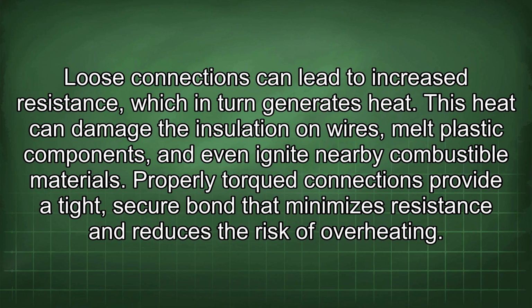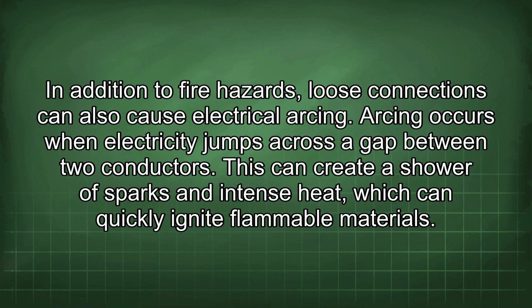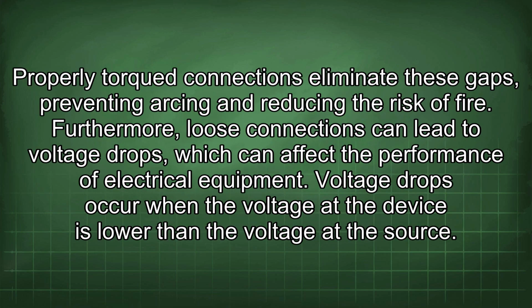Properly torqued connections provide a tight, secure bond that minimizes resistance and reduces the risk of overheating. In addition to fire hazards, loose connections can also cause electrical arcing. Arcing occurs when electricity jumps across a gap between two conductors. This can create a shower of sparks and intense heat, which can quickly ignite flammable materials. Properly torqued connections eliminate these gaps, preventing arcing and reducing the risk of fire.